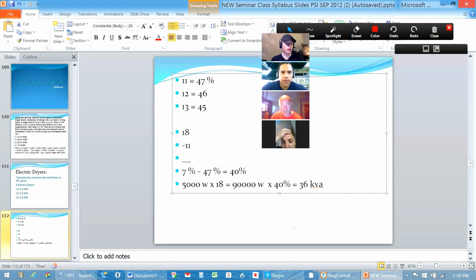But I want to caution you again that Section 220.54 is a residential dryer calculation. It is not for commercial use. In fact, there is no table at all whatsoever for commercial dryers. So if I'm doing a laundromat, I'm going to take the nameplate rating of whatever they give me.